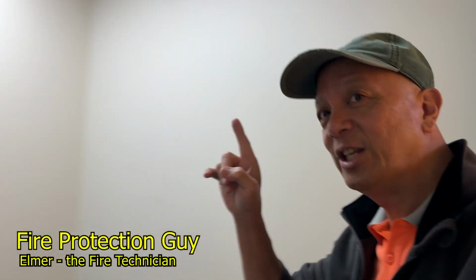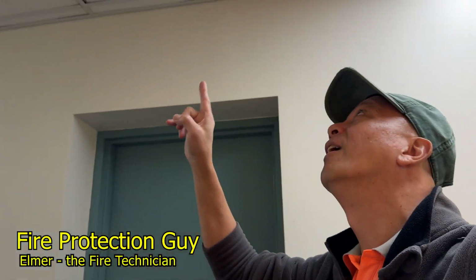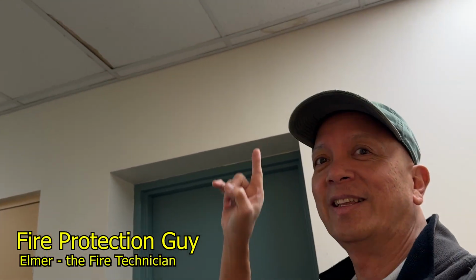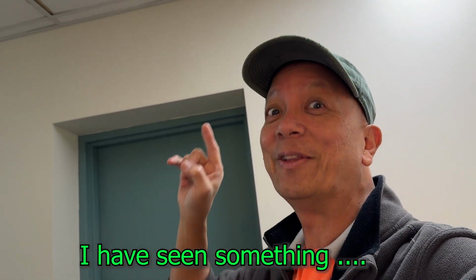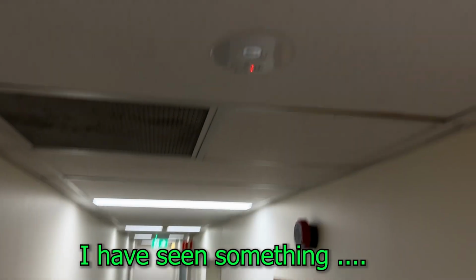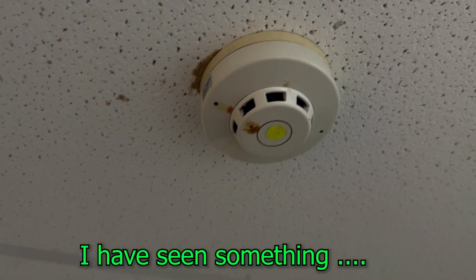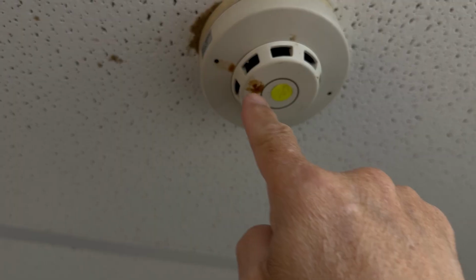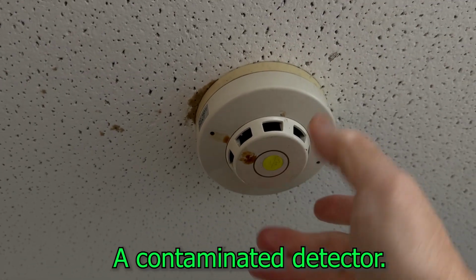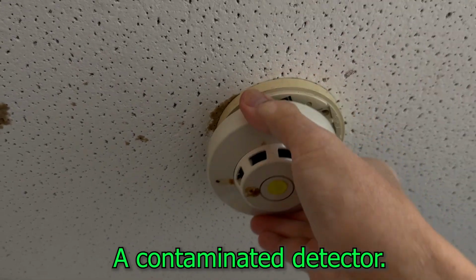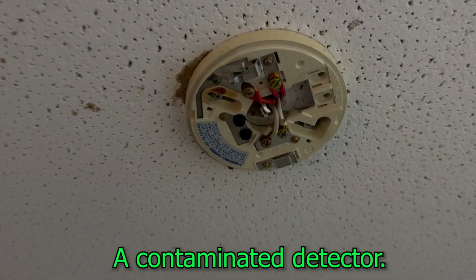But one thing I noticed is this particular detector here. There's some activity going on in the ceiling space corridor. If you notice, there's something wrong with this detector. I'll open it up. Look, this one got wet, and there's another trace.